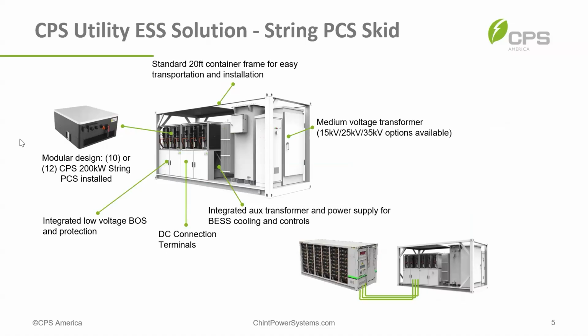Yeah, that's the other big differentiator. With the string design, you get redundancy. For utility scale, inside the battery container you have different racks of batteries, and each rack is controlled by its own individual PCS. At the bottom right you can see the individual racks in the BESS container, and each one goes to its own PCS. So if one of those PCSs has some type of issue, you're not losing your entire 5 megawatt hours, you're only losing that one 200 kW output.